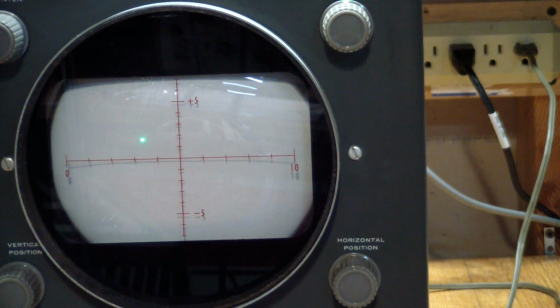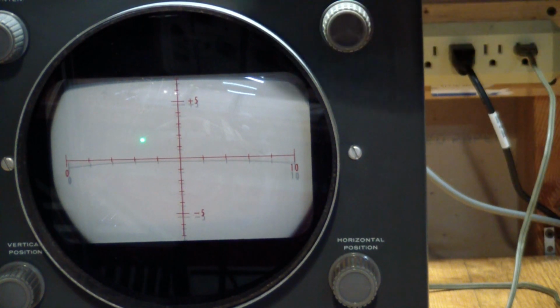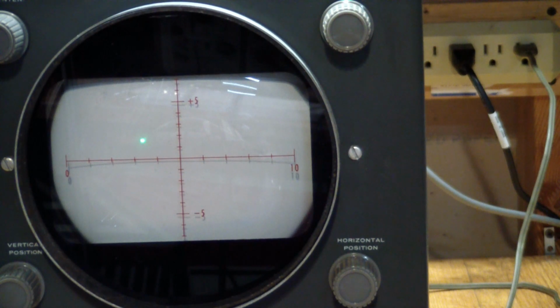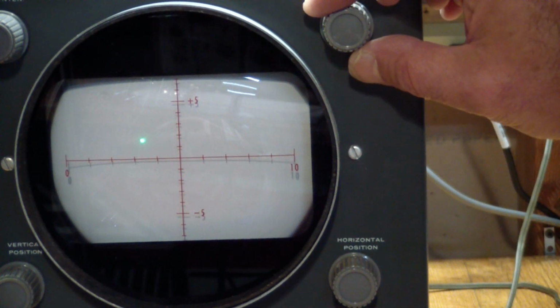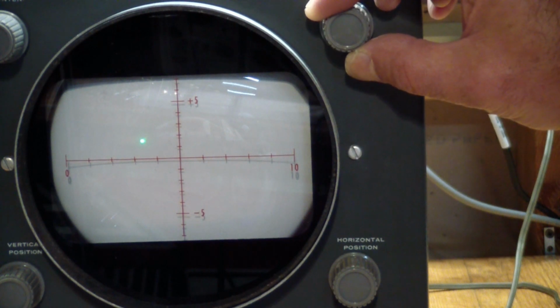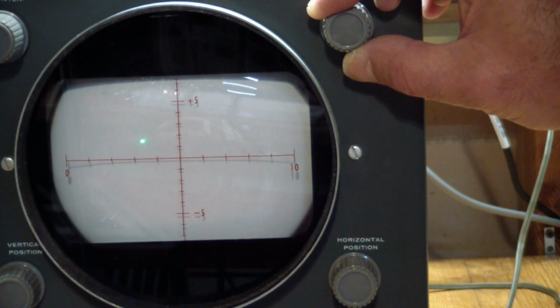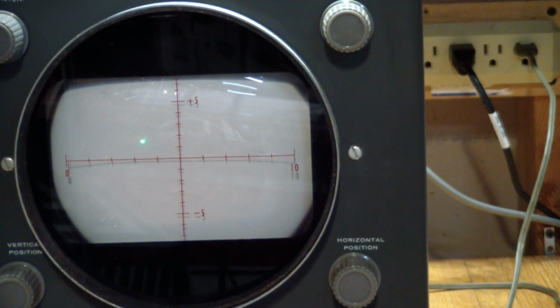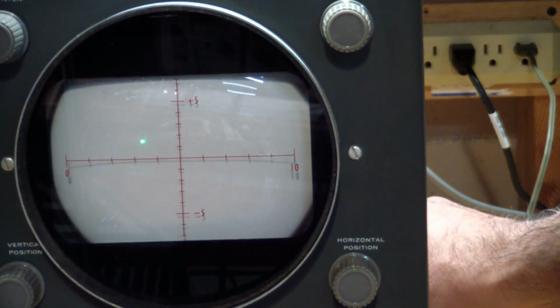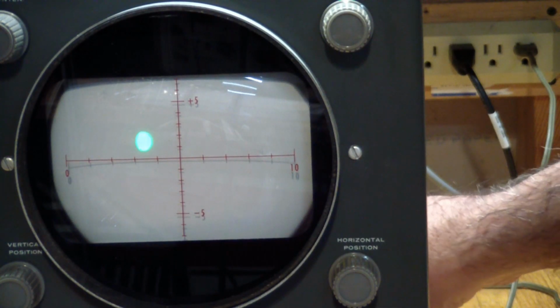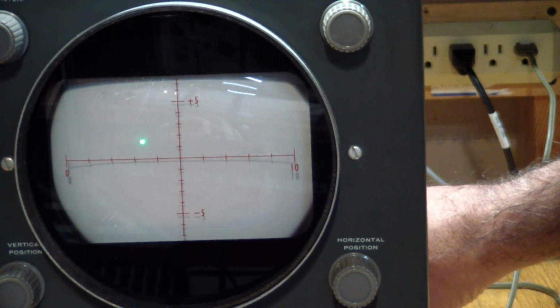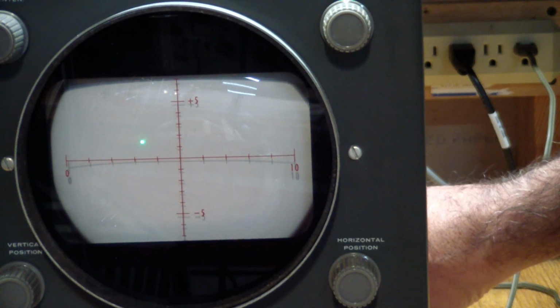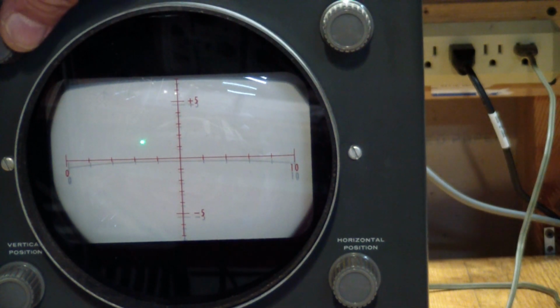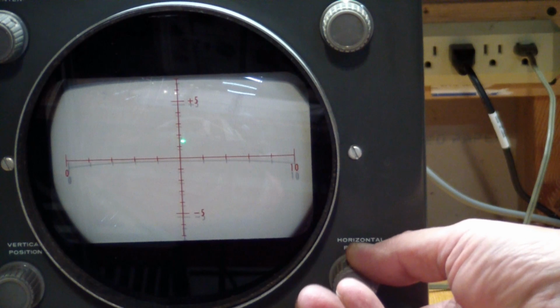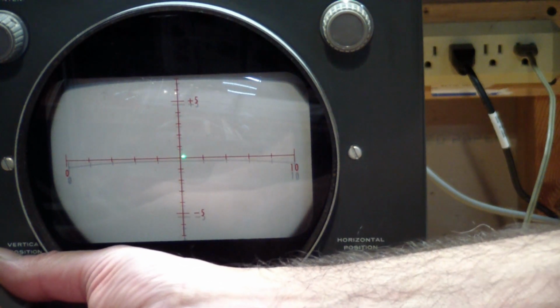I mean, you're basically supposed to adjust it using the focus, the intensity, and there's a spot-shape pot inside the device. So if we turn the focus, we make it small. I cannot see that very well on the video, but it is getting sharper. And turning the spot shape does that. So the spot shape is pretty round. And then of course you play with the intensity until you have a round spot there. And then using the horizontal and vertical offsets to center the spot.